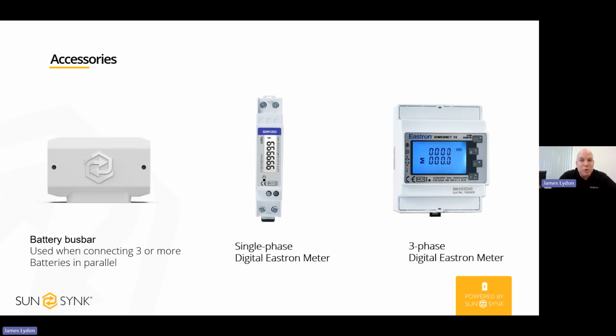But if you're installing much bigger systems, some of the single phase or like a 16 kilowatt, the max charge and discharge rate on the 16 kilowatt is 300 amps. So on the bigger inverters, you would need to size the cable from the bus bar to the inverter to the size of the inverter. If it's a 16 kilowatt, you might be at 75 mil square from the bus bar to the inverter. Again, from the bus bar to the batteries, that's fine using the cables that come with it. But from the bus bar to the inverter, you need to size that cable to the size of the inverter.